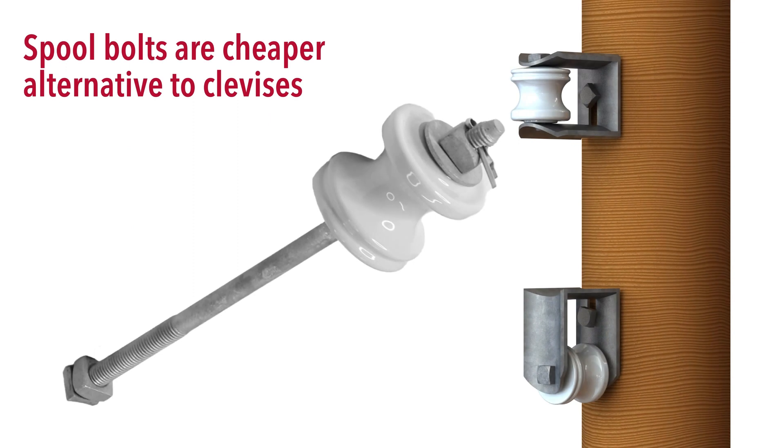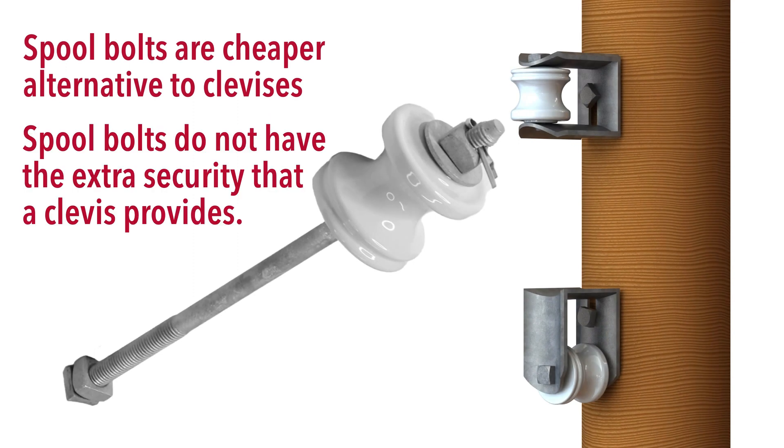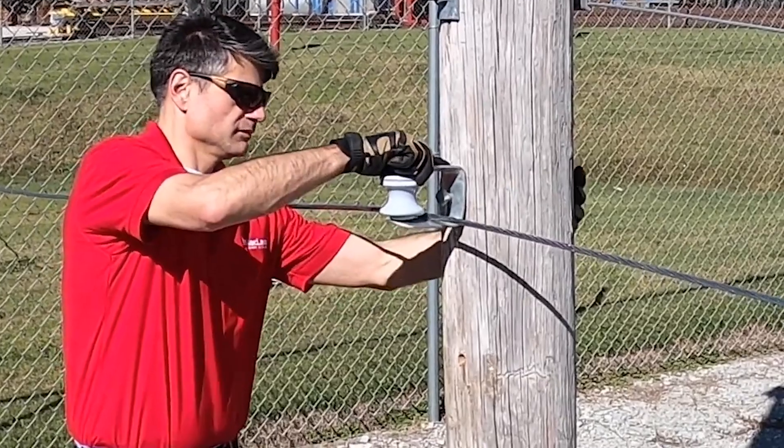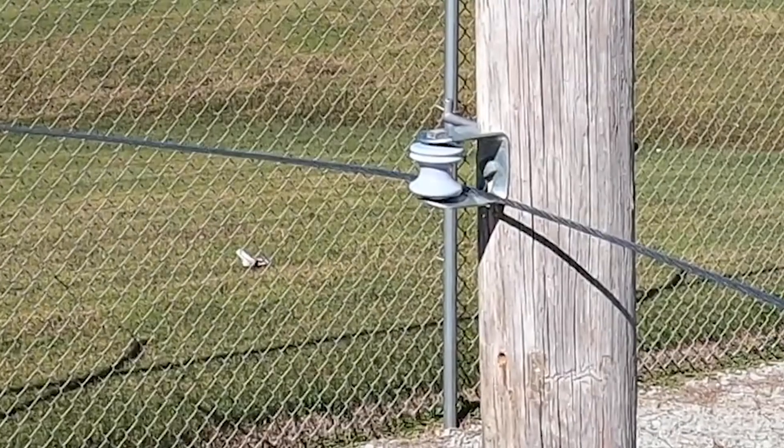Spool bolts are a cheaper alternative to clevises. However, they do not have the extra security that a clevis provides. In the rare event of a conductor slipping off of the spool insulator, the clevis body can retain the conductor and prevent it from dropping towards the ground.